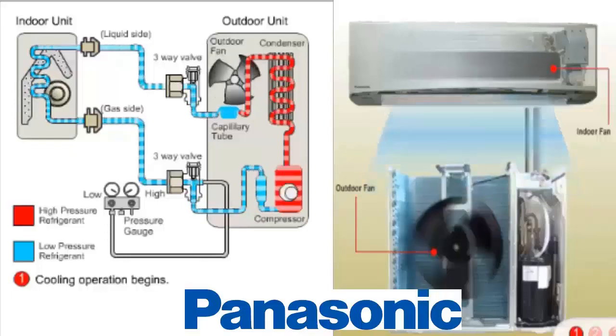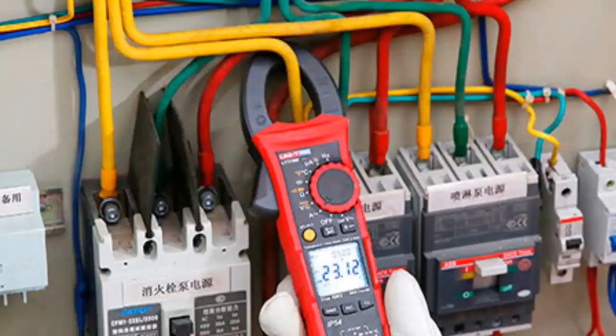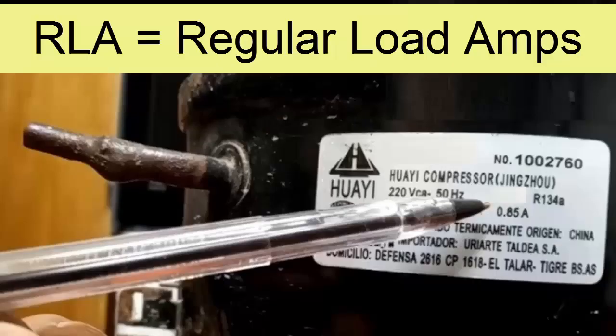Today we present what to do when the compressor amperage is higher than the regular consumption RLA. Let's begin by saying that using the ampere clamp, we can easily determine the electrical current consumption of an air conditioning unit in operation without the need to directly intervene in the equipment or have deep knowledge in the field. The value obtained with the ampere clamp should be compared to the RLA or regular equipment consumption.